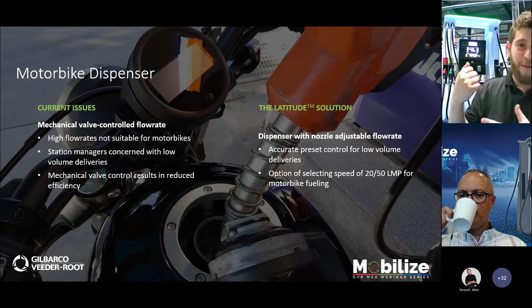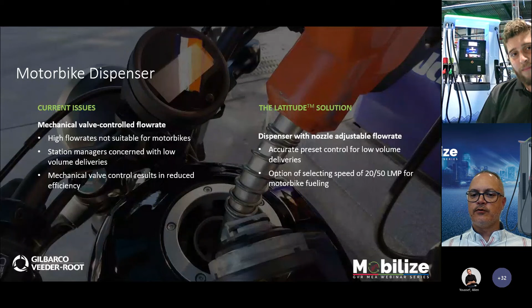The way this is solved in Latitude is a couple of things. One is having a very accurate low volume preset, so we can now do lower volumes on the preset. Secondly, there's an option to select the flow rate on the pump, whether doing motorcycle dispensing or normal fuel dispensing, between 20 liters a minute or 50 liters a minute. Combining these gives a safety feature, so you're not fueling too fast and spilling fuel, and it also gains the customer's trust that they're getting the fuel they're paying for.